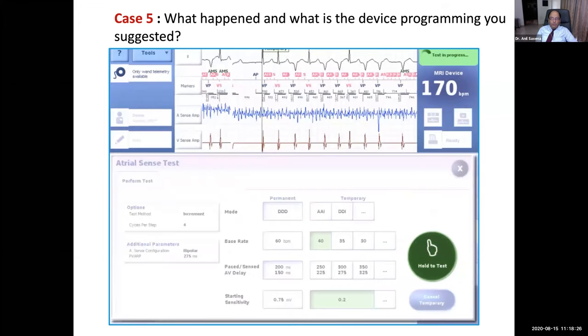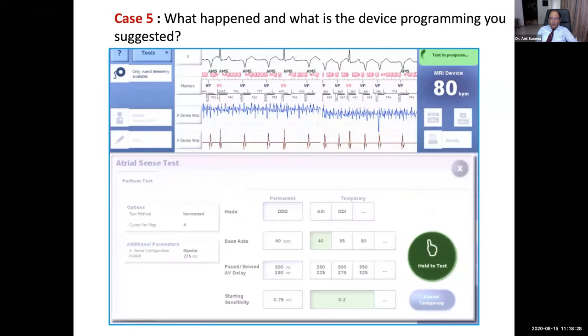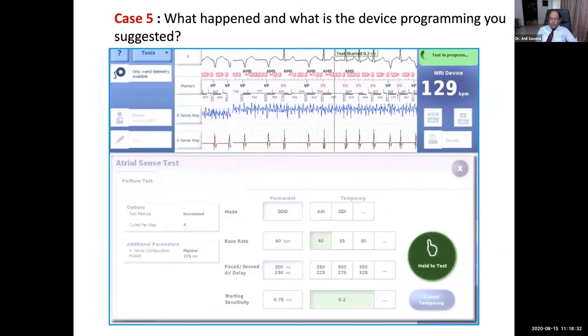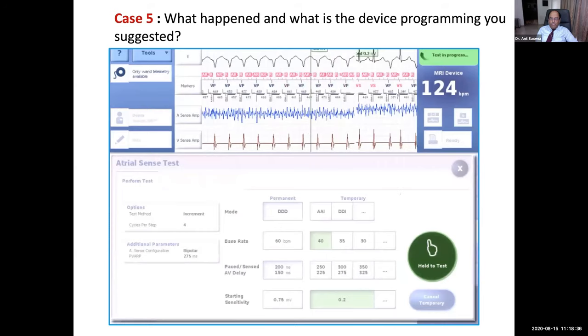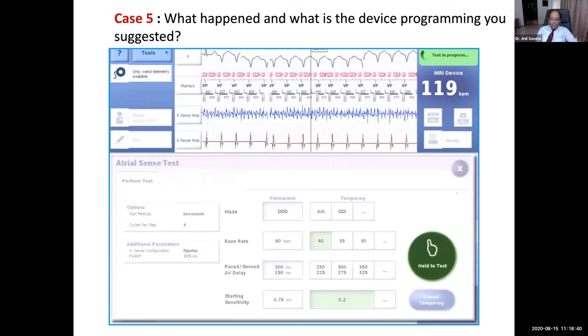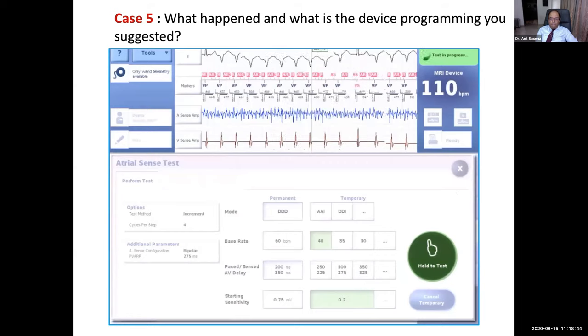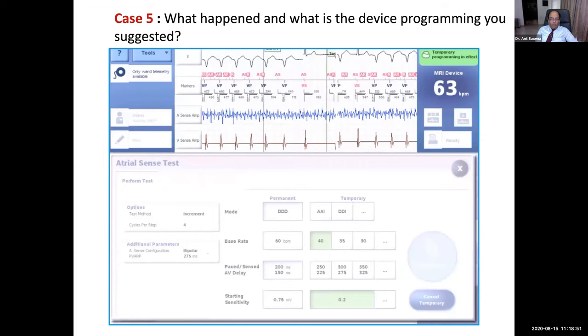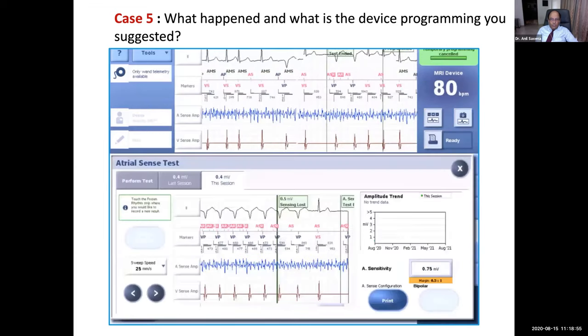On the atrial marker channel, you can see AMS also happening, and the test was started at 0.2 millivolt. Now we can see the exact amplitude of the P waves during atrial fibrillation, and we can program the sensitivity accordingly. In this example, it was around 0.3 or 0.4, and the sensitivity setting has been changed.